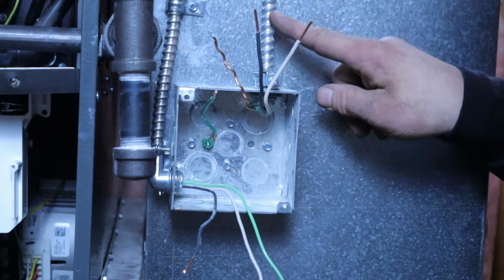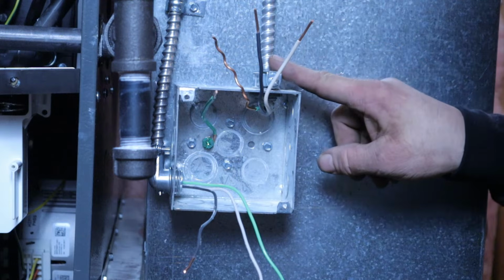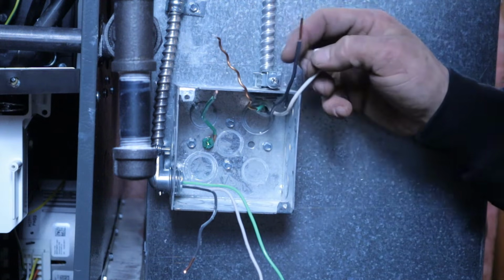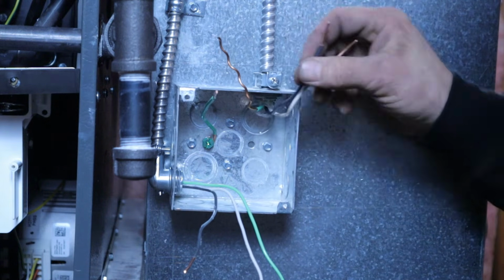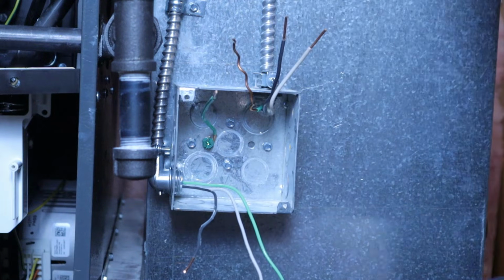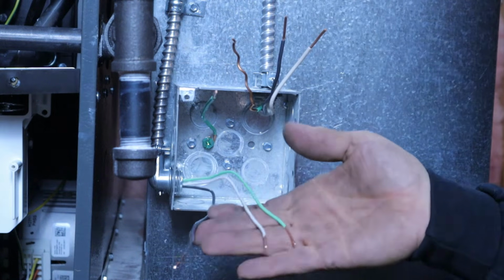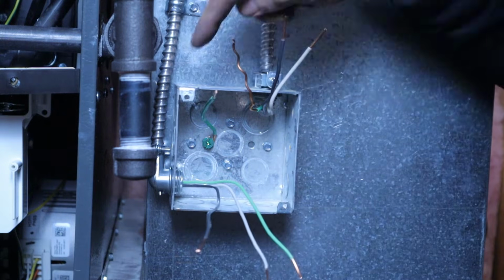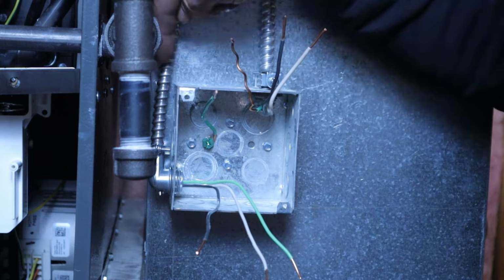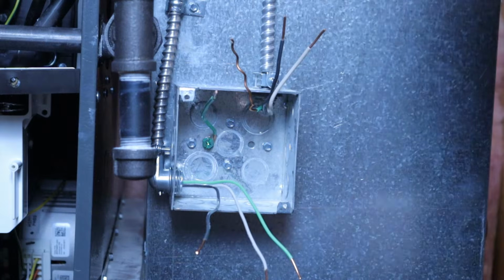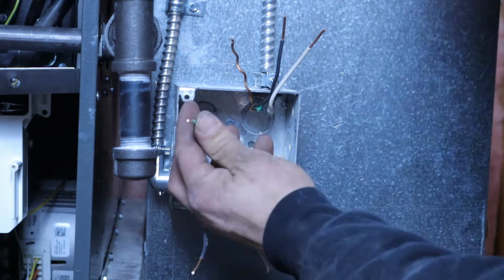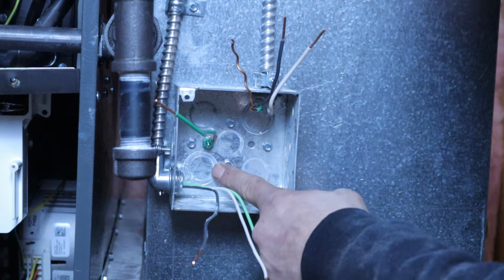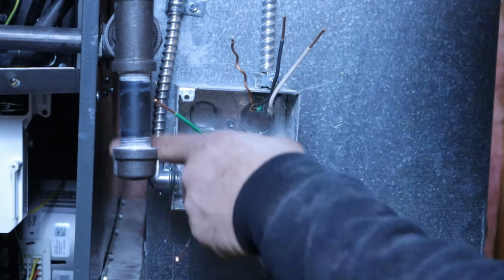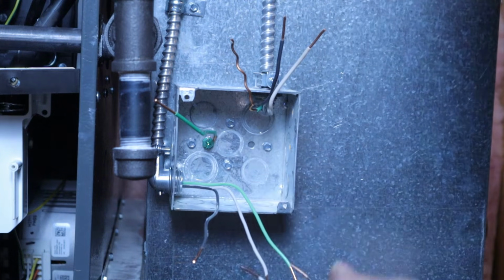What we got here, this is our power coming in for our power switch that we just wired in. We got our black, which is our hot, our white, neutral, and our ground wire. We also have our ground, neutral, and hot, and this is going back inside the furnace. I already ran that, and I'll show you the hookup there later. And this is our ground wire, grounding directly down to the metal box. Whenever you're running metal boxes, you have to ground every single one of them.